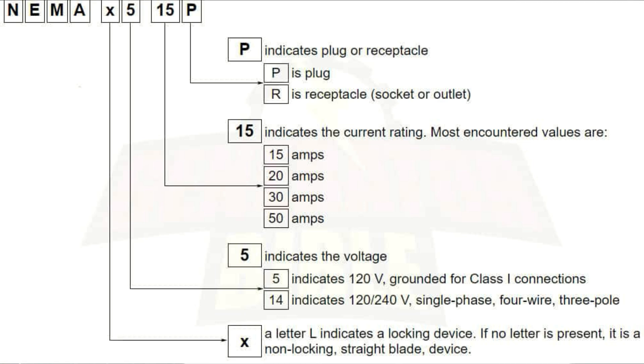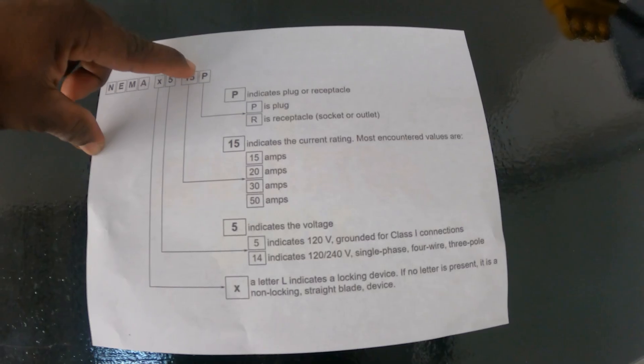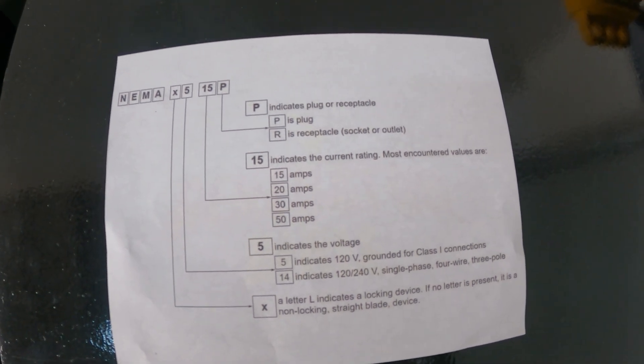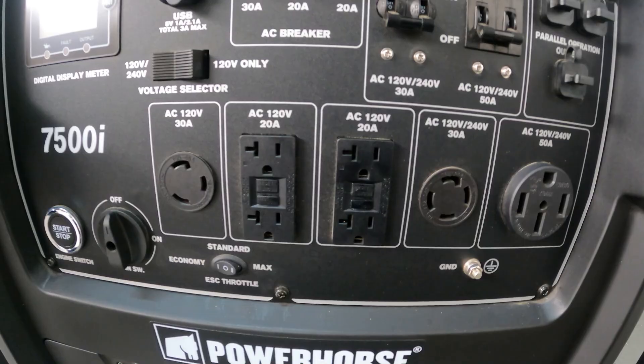Now let's explain the NEMA codes. The first letter indicates the type — locking, blade, or T-type. The number 5 indicates 120 volts; 14 indicates 240 volts. The next number is your amperage: 15, 20, 30, or 50 amps. The last letter — P or R — stands for plug or receptacle. That's the easy way to decode any NEMA name. You'll also commonly see GFCI protected outlets on generators.